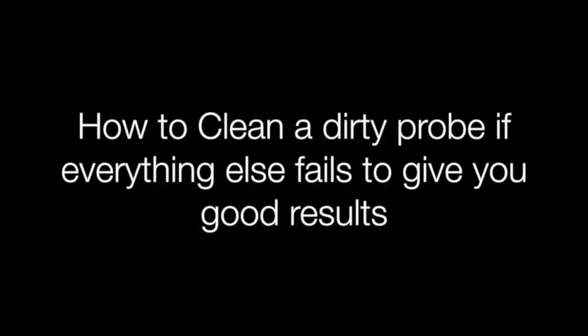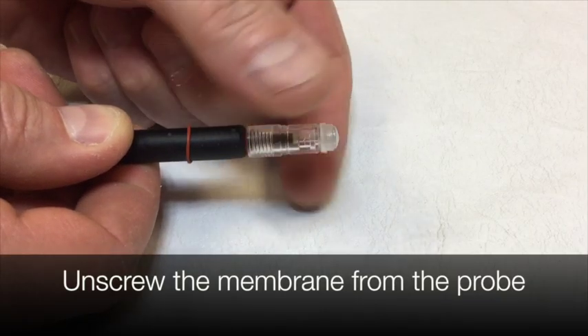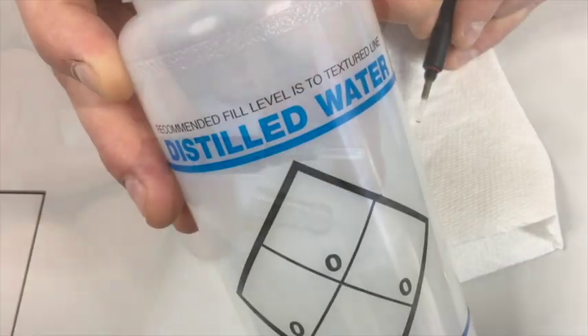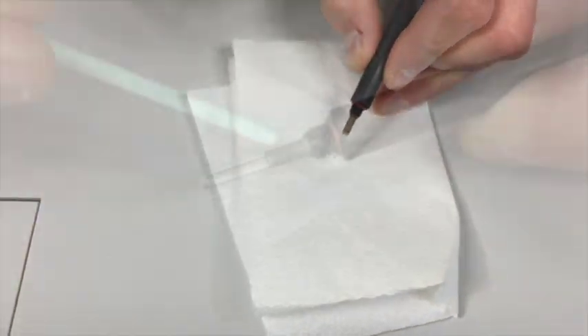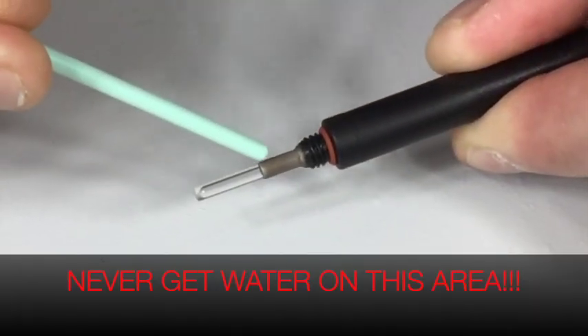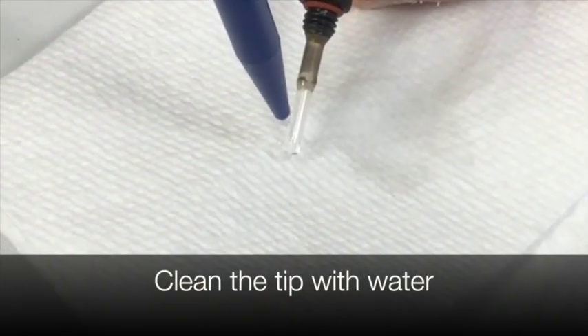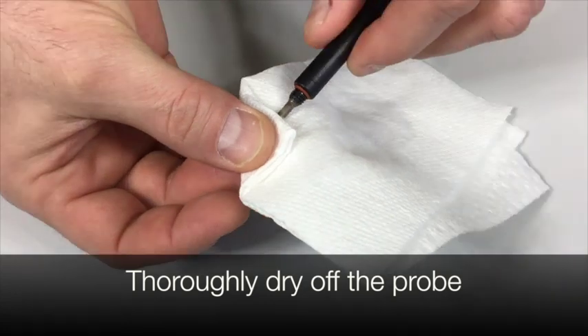How to clean a dirty probe if everything else fails to give you good results. Unscrew the membrane from the probe. Only use distilled or DI water to clean the probe. Never get water in this area. Clean the tip with water. Thoroughly dry off the probe.